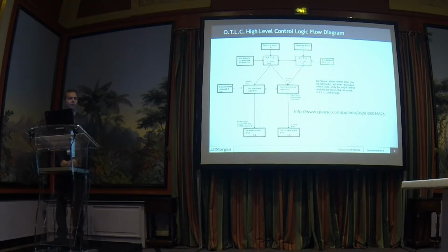And that's when I went around and I added up all these valve averages, and that's where I got 680% out of 10 machines. So then I thought, well, how are we going to fix this? And the idea I had was just to move the return air sensor into the supply air path. This is the cheap, dirty way of doing it. If you don't want to pay for reprogramming or anything like that, just move your return sensor into the supply stream and set whatever temperature you want to run it at. Instantly the machine will back off and, regardless of what comes back, it will always throw out 21.